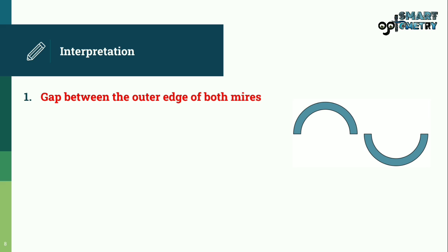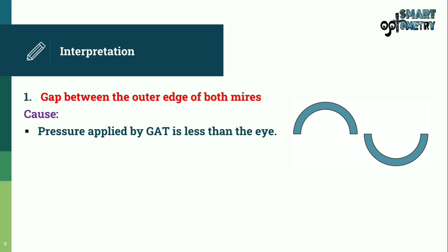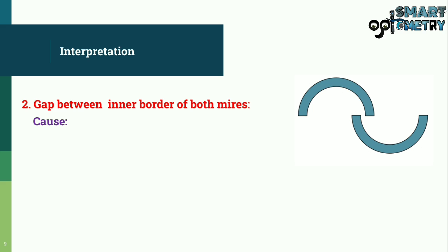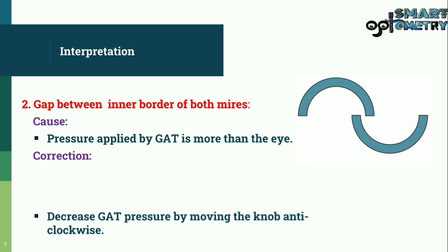At least three readings should be taken and their variation should not be more than 1 mmHg. Interpretation: a gap between the outer edges of both mires means the pressure applied by GAT is less than the eye pressure — correct by increasing GAT pressure by moving the knob clockwise. A gap between the inner borders of both mires means the pressure is more than the eye — correct by decreasing GAT pressure by moving the knob anti-clockwise.